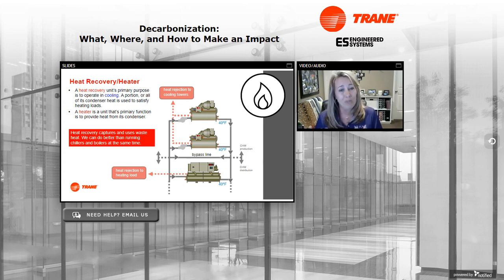A great application for these heaters is in a large chilled water plant. Like I said previously, we almost always have a need for hot and cold water year round. So I'll add this heater to my large chilled water system. The heater is acting as a heater, loading and unloading based on the heating load of the building. And then the cold water that it's producing is sent upstream in the system to help those chillers that are providing the cold water become even more efficient. Adding a heater to a large chilled water system is a must anytime there's a heating load at all. Being efficient is really the key to being successful here.